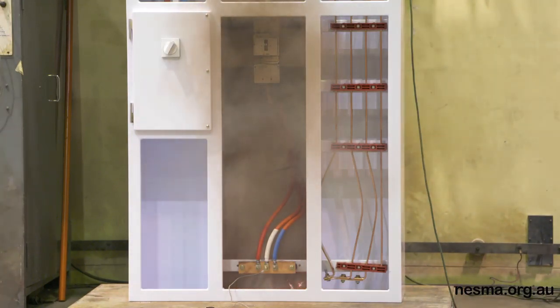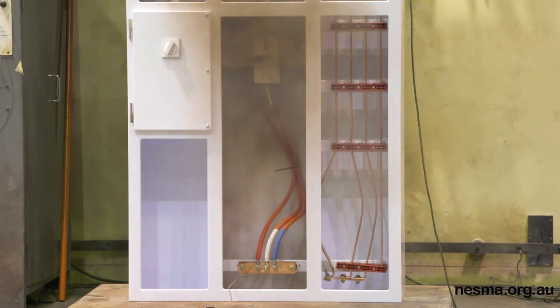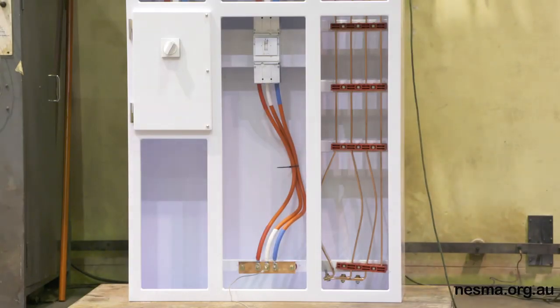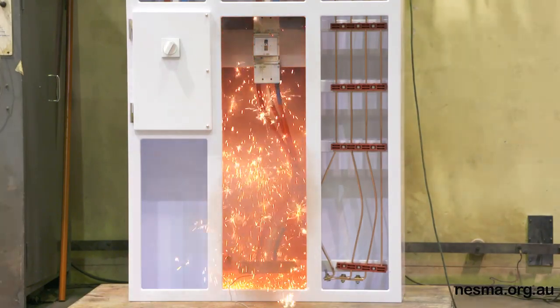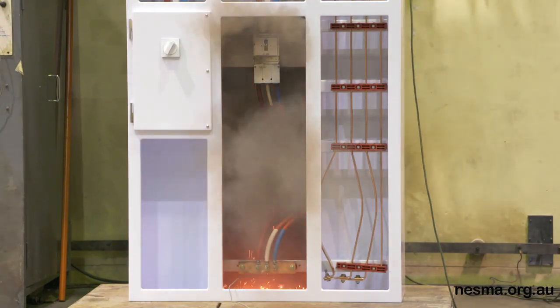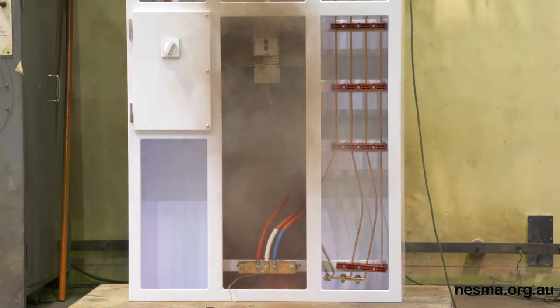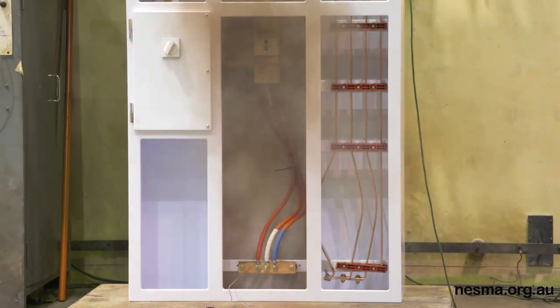So that's one of the unknowns for a lot of people that are just building their switchboards and come to the test station the first time, the amount of pressure that is generated inside a circuit breaker enclosure. What you've got to remember, the arcing at the contacts, you're superheating the air and then it's expanding at a great rate, so pressurising the whole enclosure. Now, of course, the smaller the enclosure you put the circuit breaker in, and without ventilation, that pressure wave, due to the expanding air inside the chamber, is going to hit walls, sides, doors of the enclosure at the same ferocity, and that's where it starts putting a lot of pressure onto door hinges and door fastenings. And we'll see that with the next test anyway.